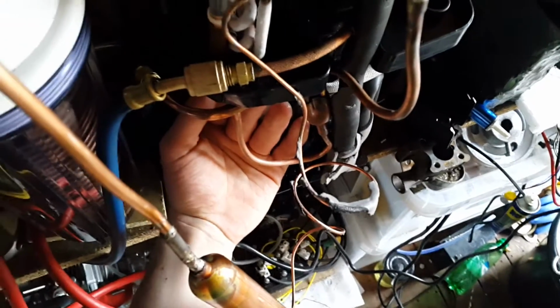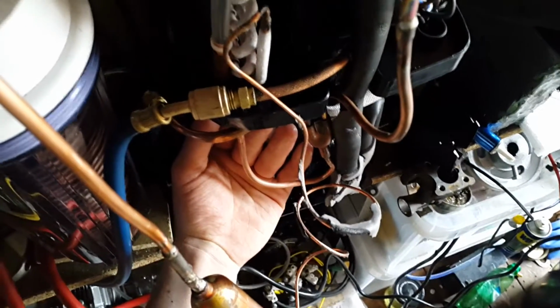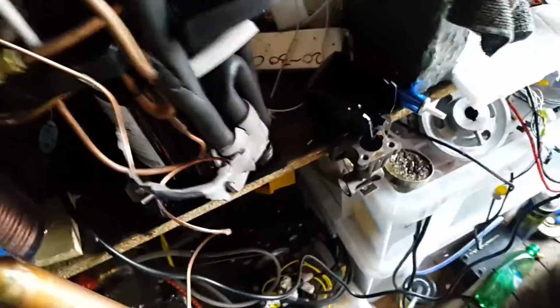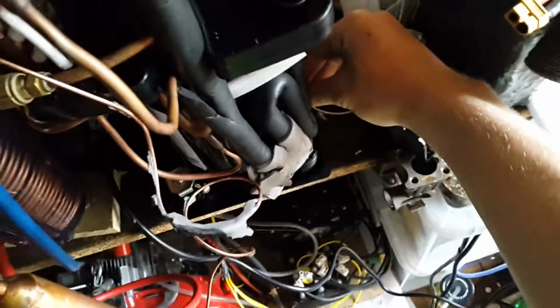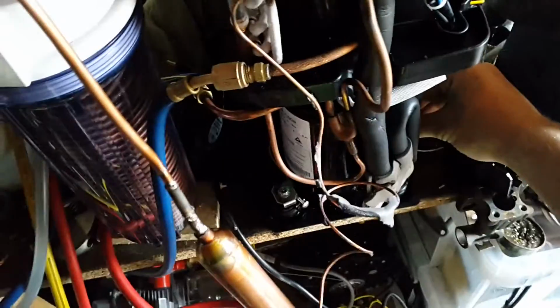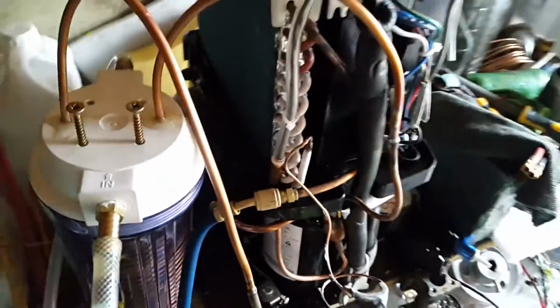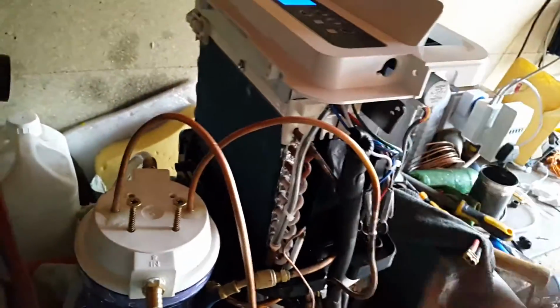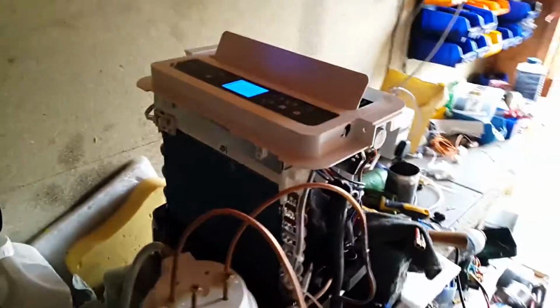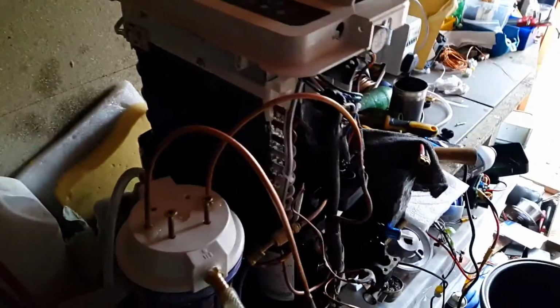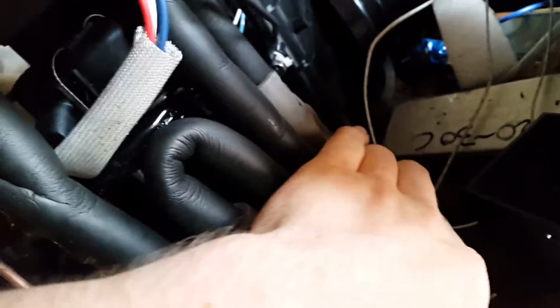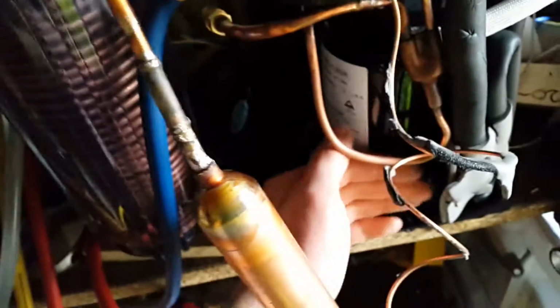The compressor is actually fine just now. It's very warm, but I could keep my hand on it, and that is because I'm getting really cold refrigerant returning to cool it. But if the ambient temperatures go up too high and the discharge pressures go up too much, we're not going to get the cooling. Now I've just got the very difficult task of getting the casings back on. But as you can see, there's condensation all the way right up to the compressor, nice and cold.